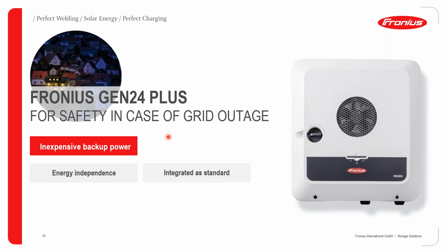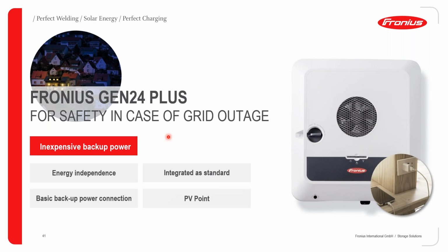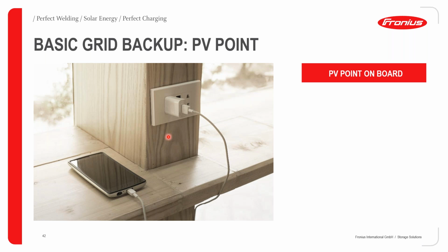We will be looking at the PV point in a bit more detail in the next slide, but this is also to give you an indication that the Gen 24 offers you very good flexibility, in that you can start an installation with or without a battery and still be able to get inexpensive power backup from this system. So when you come to the PV point, what are the specific features of the PV point? This is already integrated as a standard feature in the Fronius Gen 24 inverter. And the PV point, for your information, is only supplied if there is a grid outage.